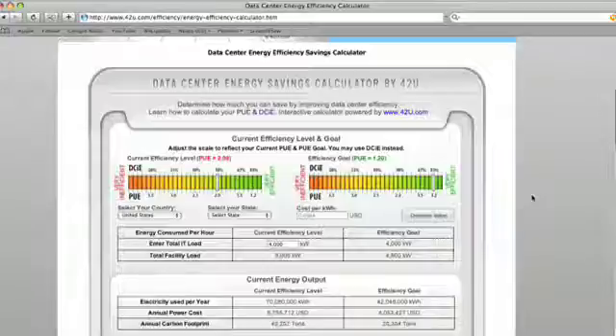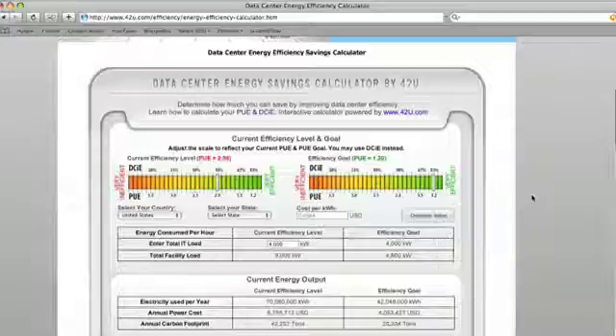A PUE of 2.0 means that for every watt delivered to IT equipment, another watt is expended in cooling or distribution. With PUE, the smallest the number approaching one, the better. Our calculator is driven by these two values.